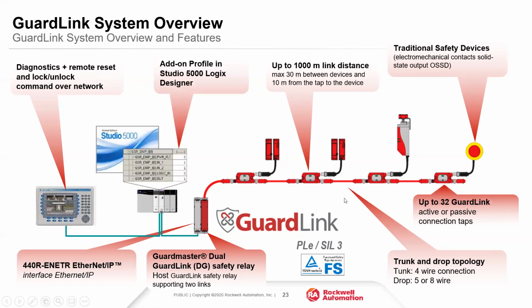And of course, there's an add-on profile for this in Studio 5000. So all these devices that are out there on GuardLink, you can easily pull that information in through the add-on profile. The add-on profile allows you to connect to that DG and then go out and upload and see what's out on that GuardLink network. You don't have to add each one individually to the program. It will go out there and scan it for you, again, to increase the speed to commissioning. So that's a quick overview of what you would do with products that don't have CIP Safety over Ethernet.